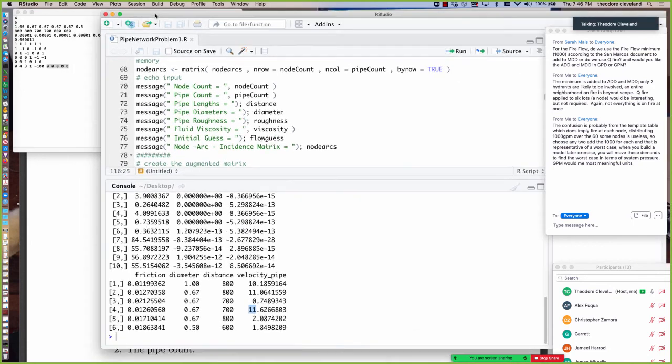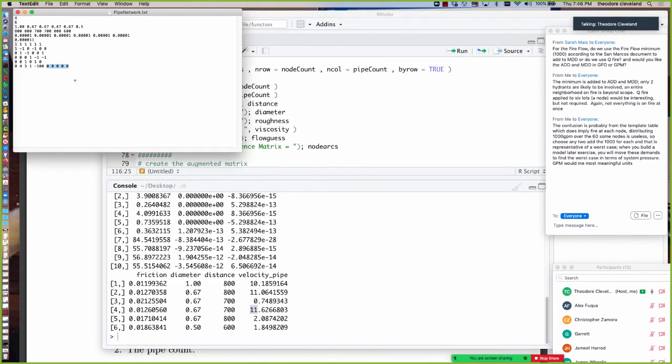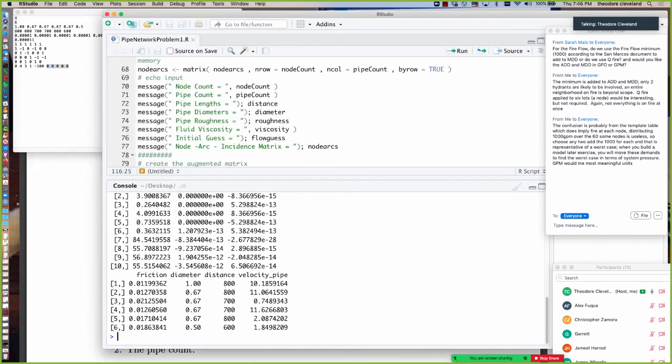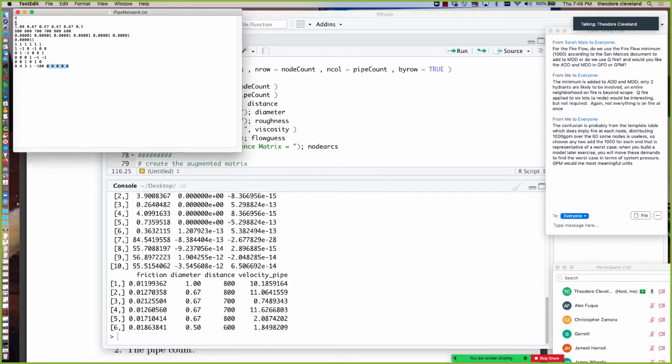Okay, so that's just a lot of calculation. What was the point of that? Well, the first is we observed that for pipes 1, 2, and 4, the velocities are too big. So let's increase their size a bit. We'll make pipe 1 1.5 feet. It says 2 needs to go up. We'll make 2 1.5 feet. And 4, we'll make it a big pipe.